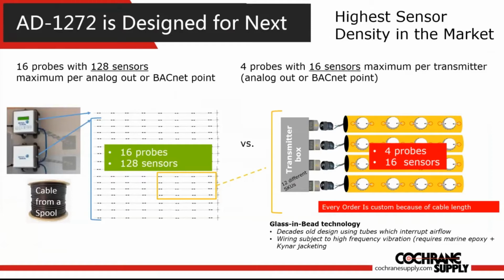So in our system over here on the left, we have a primary probe, an ancillary probe, which is wired through a daisy chain connection using non-proprietary cable. So we could have one probe with 8 sensors, or we could have up to 16 probes with 128 sensors. If you wanted so many sensors that you're sure you're getting all the airflow in that system, you could have that many as a custom.